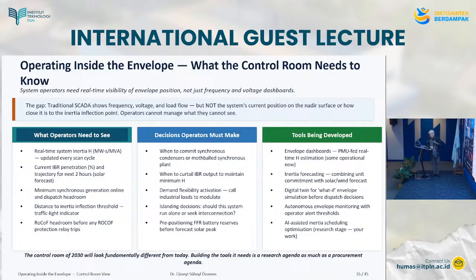The operators need to see system inertia updated every scan cycle for current IBR penetration, so they have to see what IBRs they have in the system for the next 2 hours. That means solar forecast. Okay, this is what the operators need to see for high renewable-dominated systems: real system inertia, updated every scan cycle, current IBR penetration, solar forecast, minimum synchronous generation online or headroom dispatch, and distance to the inertia inflection threshold, like a traffic light indicator, like the graph I showed before. There's the green zone, orange zone, and the red zone. Rate of change of frequency headroom before any rate of change of frequency protection relay trips. So this is what the operators in a renewable energy dominated system need to see.